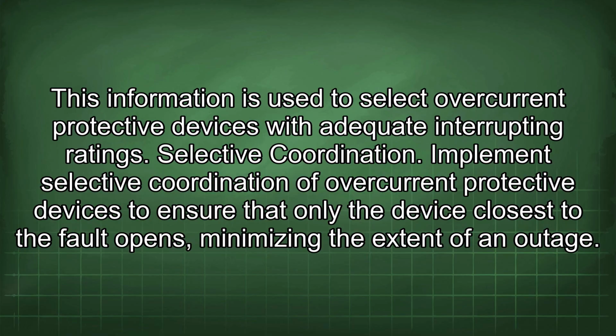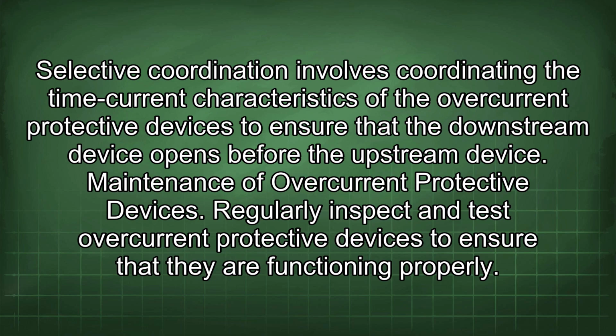Selective coordination. Implement selective coordination of overcurrent protective devices to ensure that only the device closest to the fault opens, minimizing the extent of an outage. Selective coordination involves coordinating the time current characteristics of the overcurrent protective devices to ensure that the downstream device opens before the upstream device.